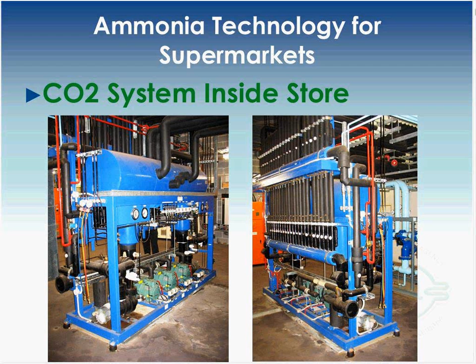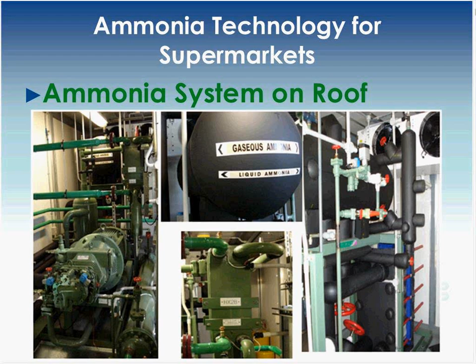This is an example of a scenario where the equipment is actually on the roof in an enclosure, in this case something like a mechanical room. Other items manufacturers would consider include weatherproof cases, much like rooftop equipment typically has, and enclosures with removable panels, so that you essentially have the operation as an indoor application.